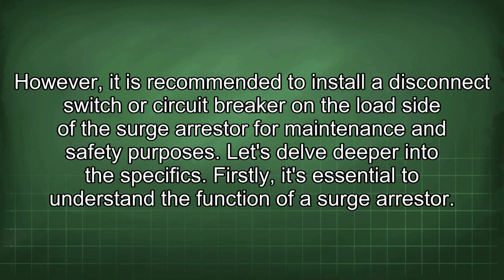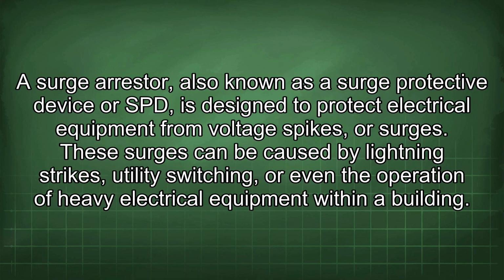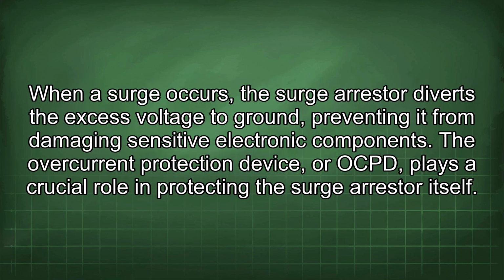Let's delve deeper into the specifics. Firstly, it's essential to understand the function of a surge arrestor. A surge arrestor, also known as a surge protective device or SPD, is designed to protect electrical equipment from voltage spikes or surges. These surges can be caused by lightning strikes, utility switching, or even the operation of heavy electrical equipment within a building.